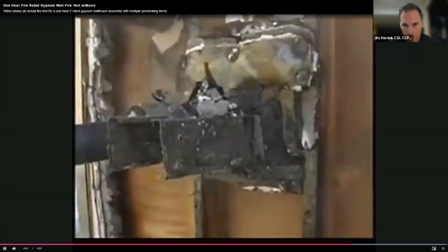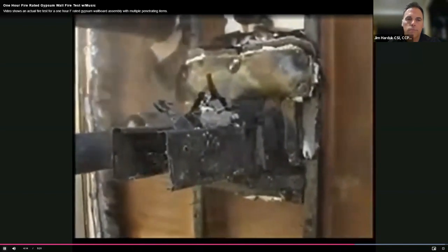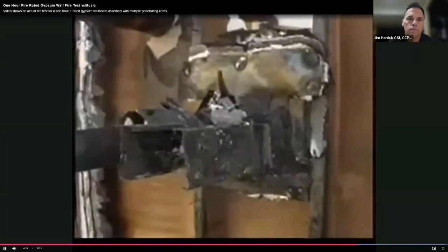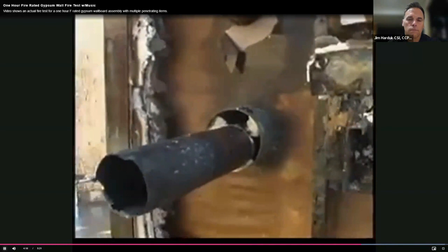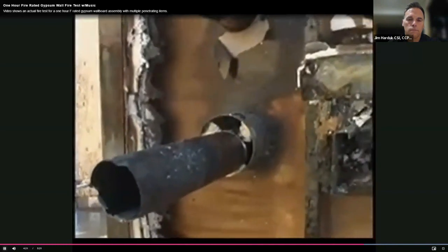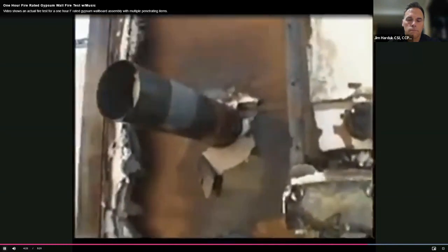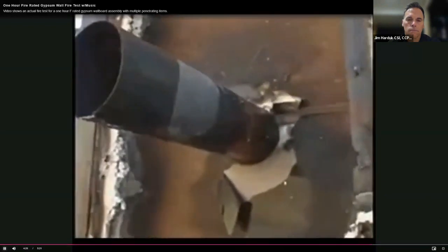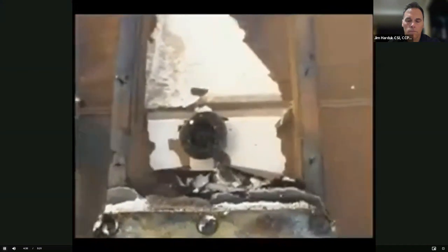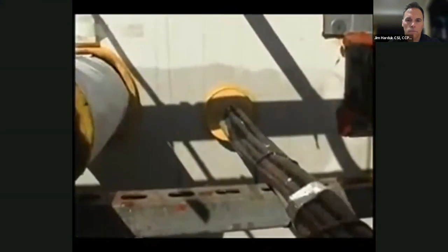The fire exposure side is being shown. You can see the severity of the fire and the hose stream by looking at the charring on the wood studs. The insulation and cable jacketing is burned away. You are looking at the non-fire side of the wall. The penetrations and fire stops have remained intact.